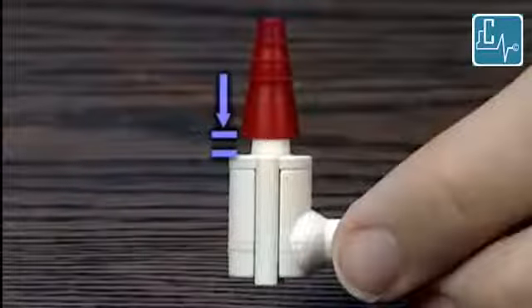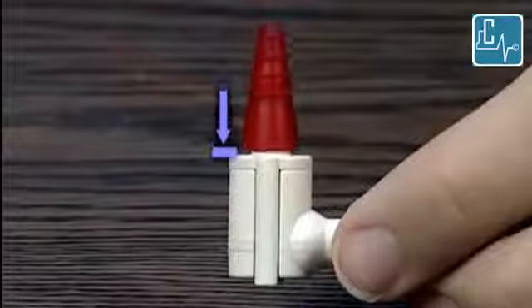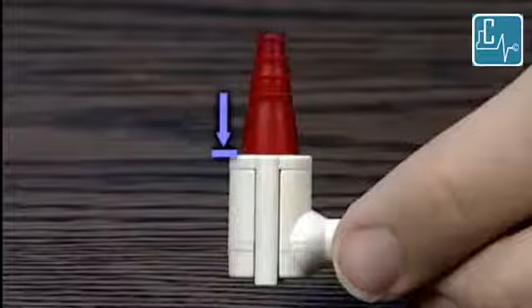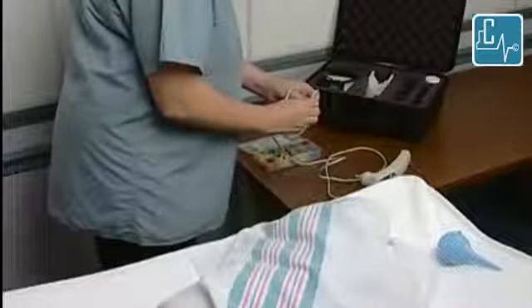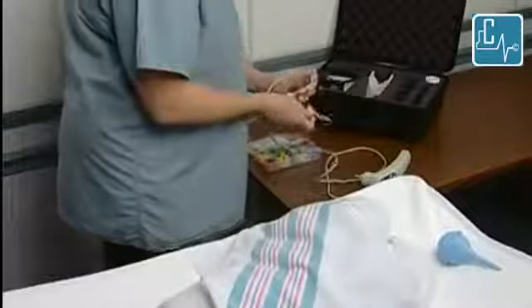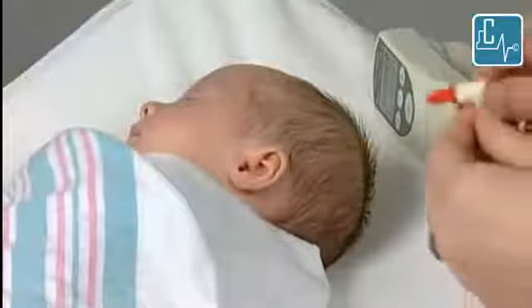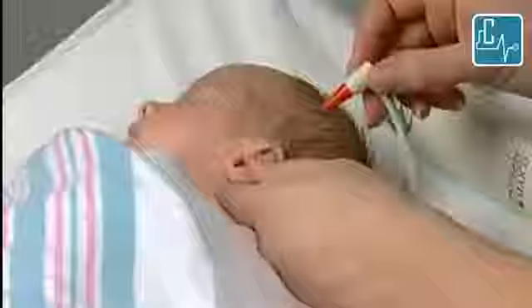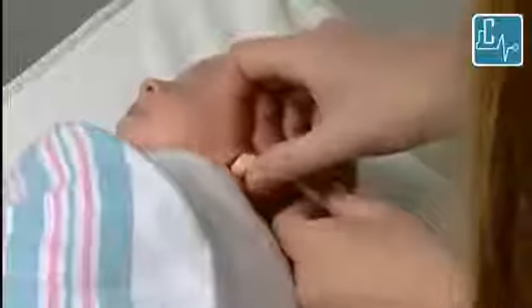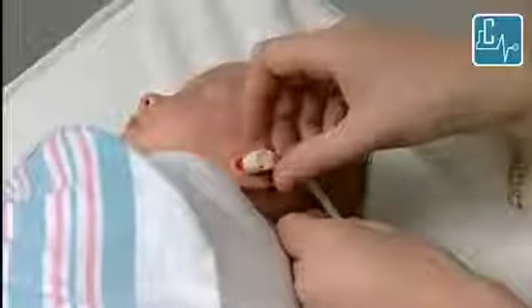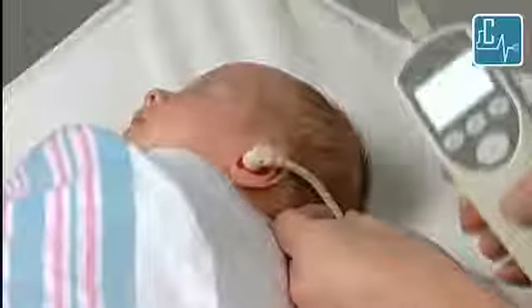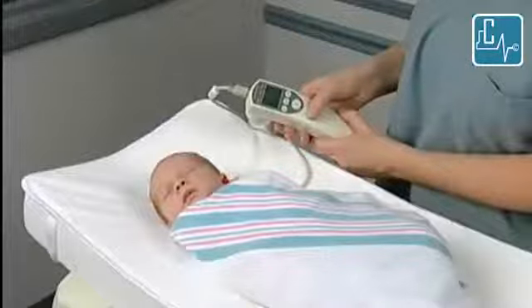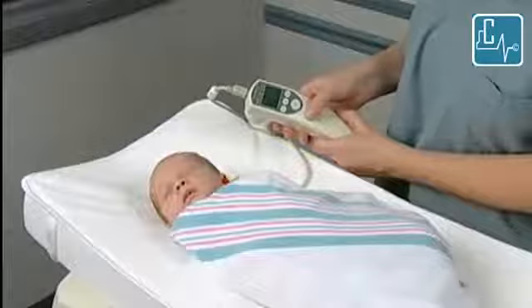If there is any space between the probe tip and the ear tip, the test will not run correctly. To properly place the ear tip in the newborn's ear, first pull down and back on the pinna. This will straighten the ear canal and make probe placement more effective. Now, gently place the probe in the newborn's ear, making sure the probe is at the proper angle. As a general rule, the probe should be angled toward the infant's nose.